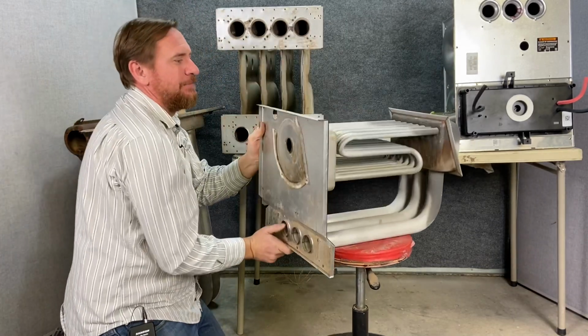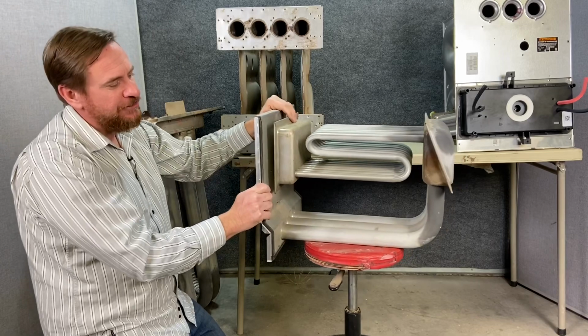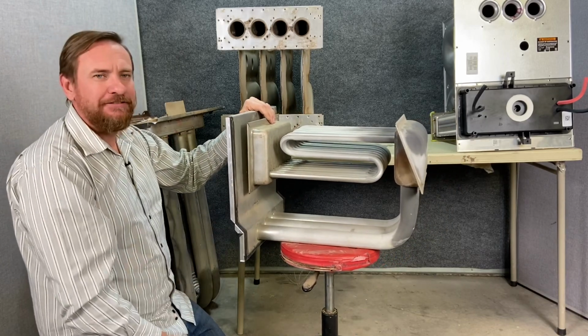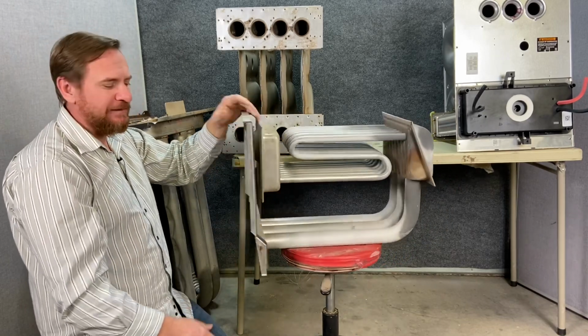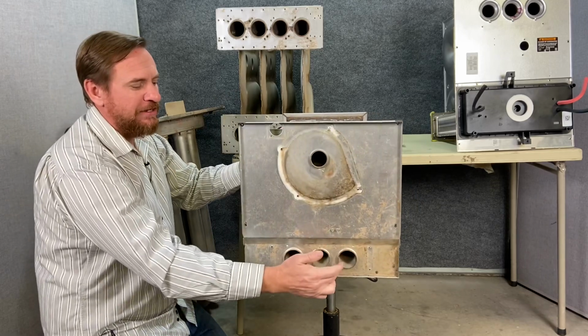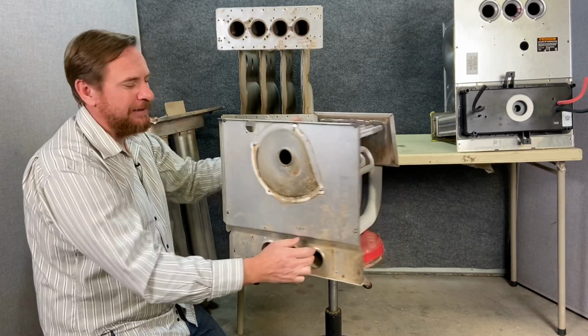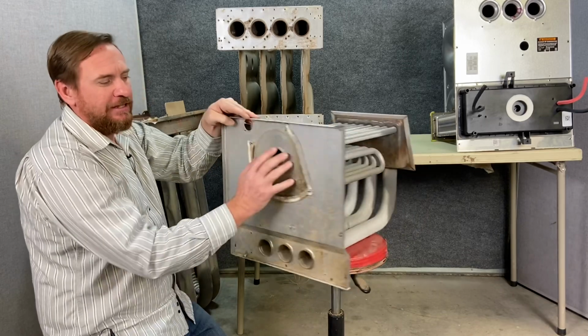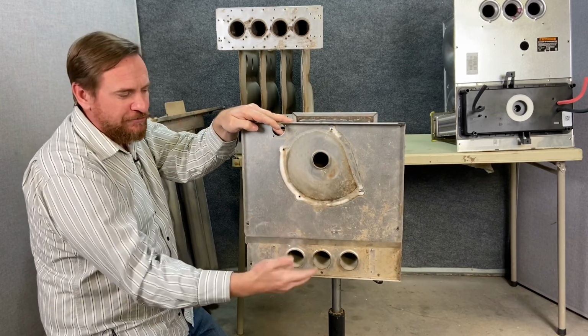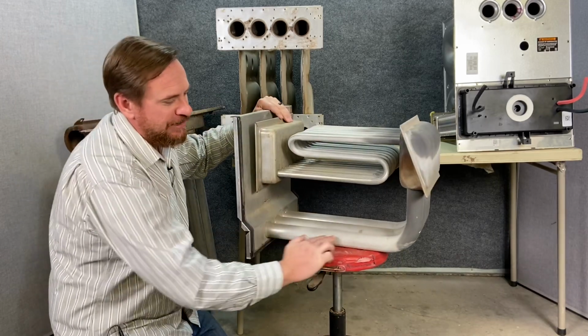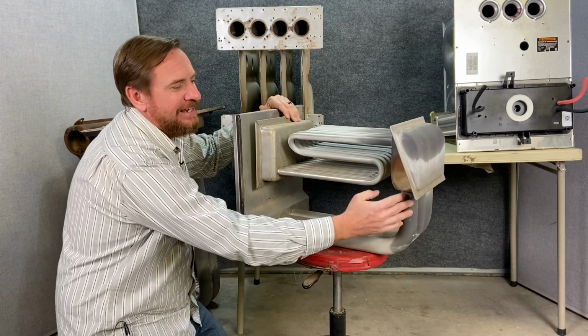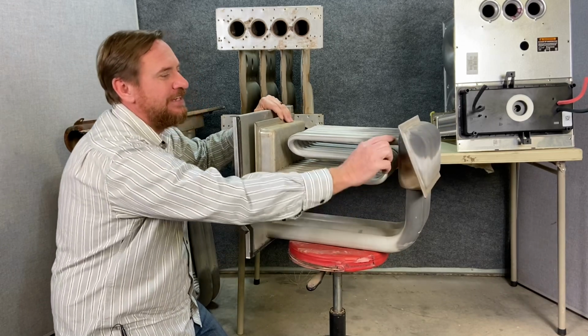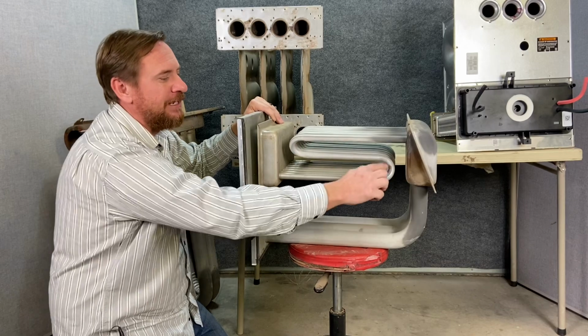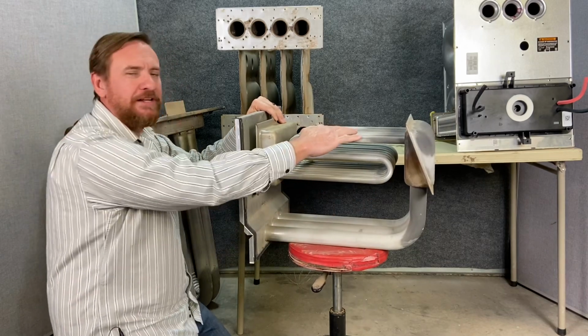This is also an 80% gas furnace heat exchanger. That's a different brand from a different manufacturer. Still works the same way. In the very bottom is where we would have our in-shot burners throwing our flame sideways. Inducer fan motor at the top, pulling the draft through. Our combustion chamber is here. Our hot gases collect in this little collector box. And then from there, we ran our tubes, a lot smaller and more quantity of these tubes.